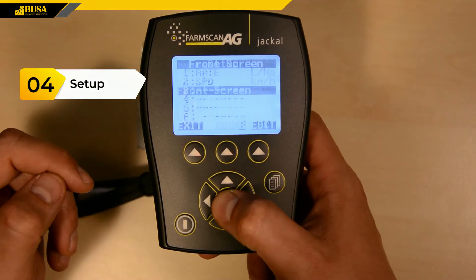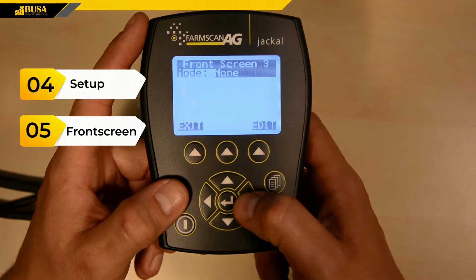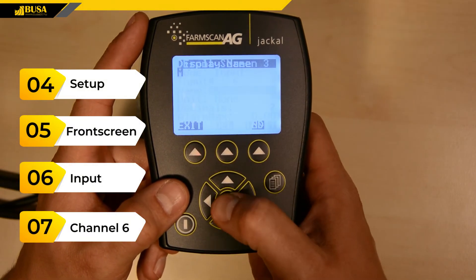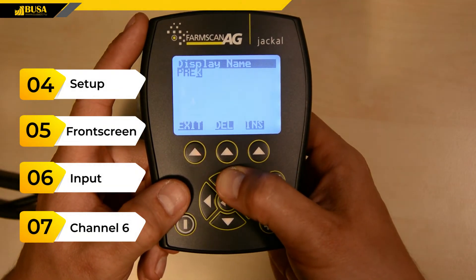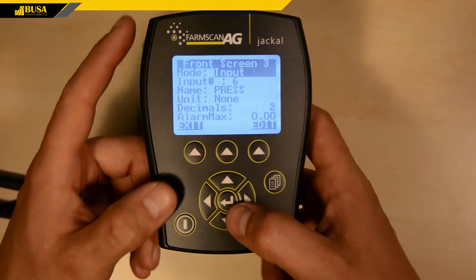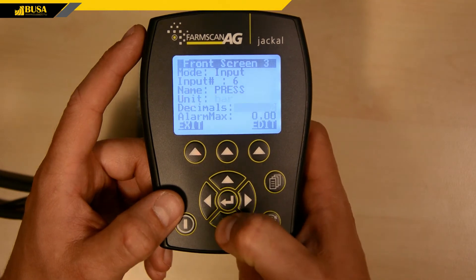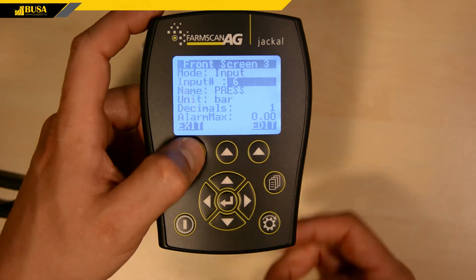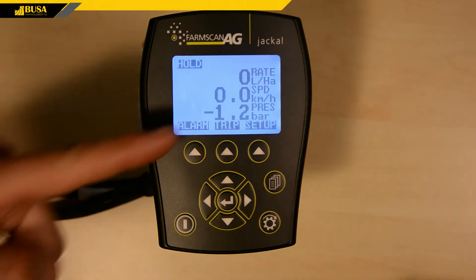In the Setup menu Front Screen Item, choose a free row. Set the mode to input and select the input. Choose Channel 6 and give it an arbitrary name. Choose the units and set how many digits the value should have after the decimal point. In our case, the sensor is not plugged in, so the value is negative.